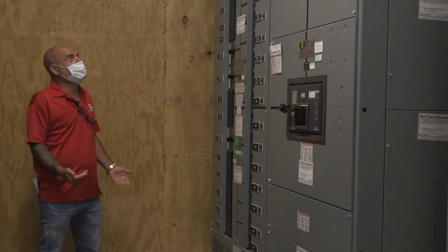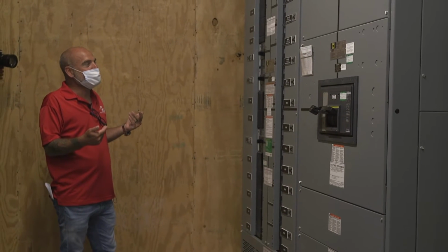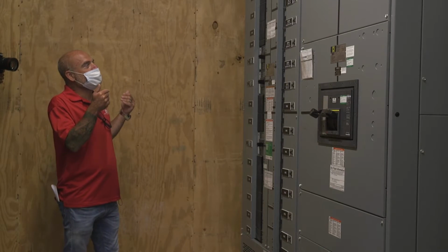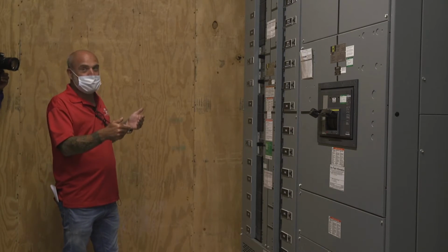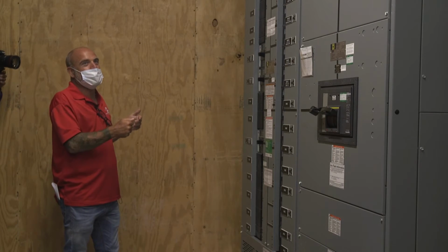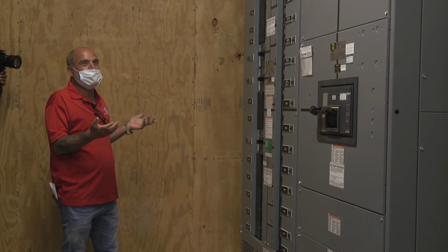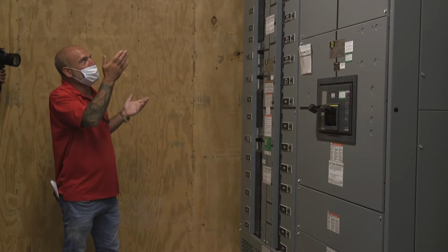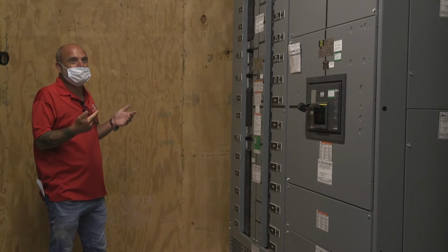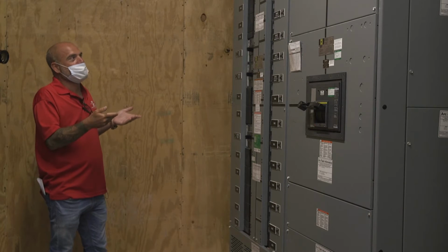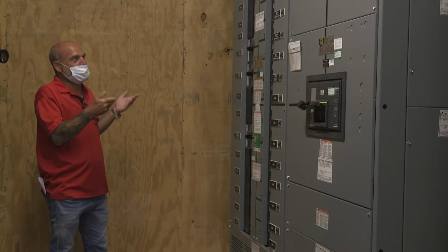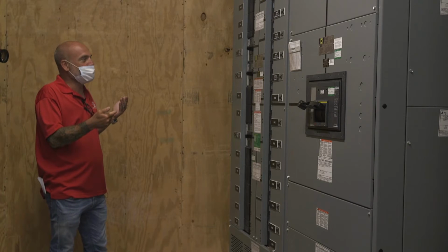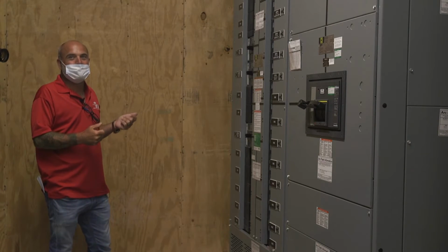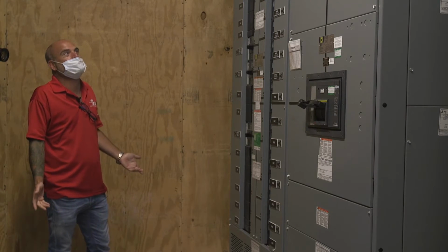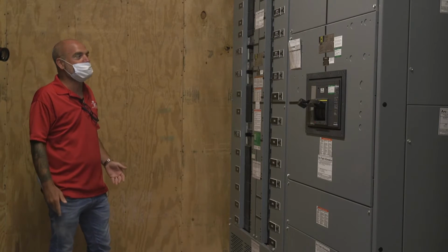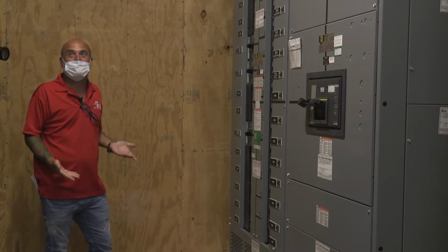Circuit breakers really don't need maintenance. The only thing you really have to worry about on the breaker is the torque of the lugs, and usually you use an IR heat detector. If you're doing your annual once a year maintenance, you would check all the lugs and look for your hot spots, because 90% of the time if something is going to burn out, it's where the hot spot is. So torquing these to the right foot-pounds is the most important maintenance item on a switchboard and circuit breakers. Breakers are pretty much maintenance free.